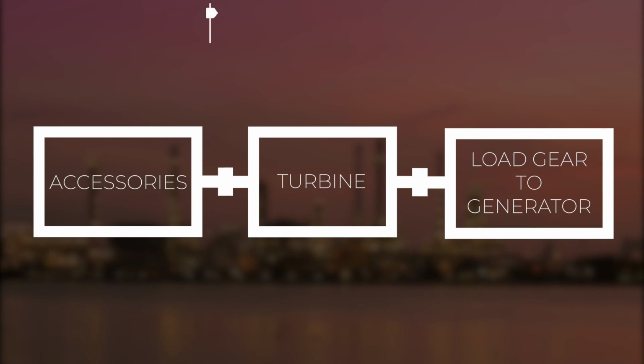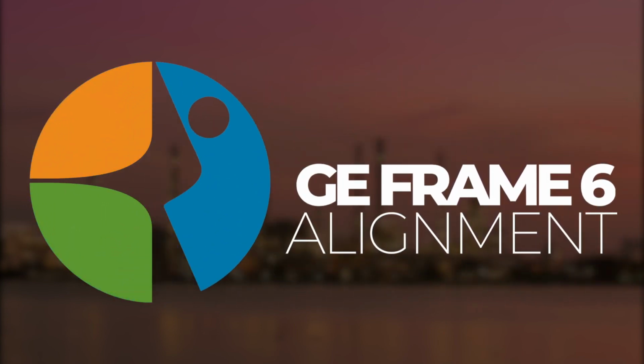At this point, we will take alignment readings at both the couplings and at all the other components to have a final as-left set of alignment readings. We must always end on a reading, never on a move. That's how we complete a GE Frame 6 gas turbine alignment.